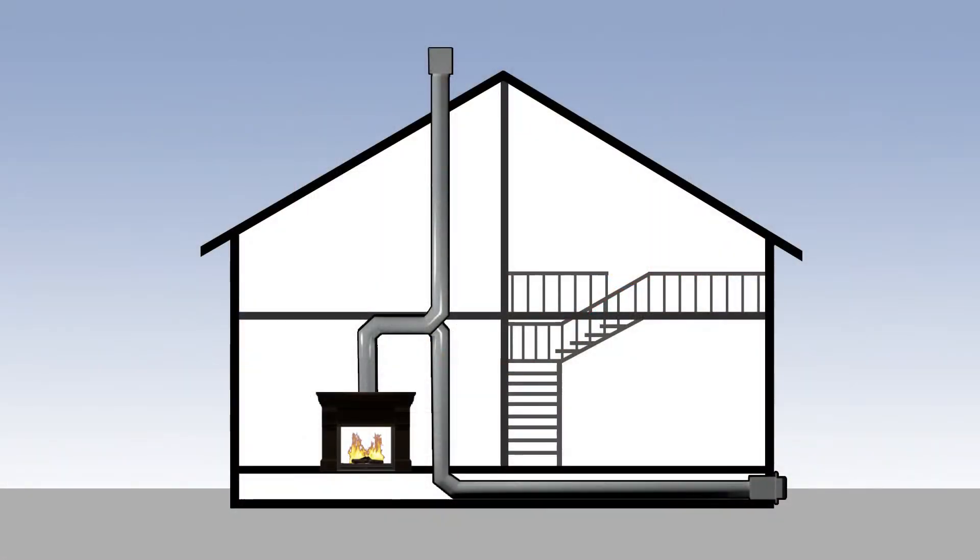The power vent accessory, mounted either vertically or horizontally, increases the allowable vent run from 40 feet up to 100 feet, allowing vent runs in any direction, even down. This opens up a world of installation possibilities.